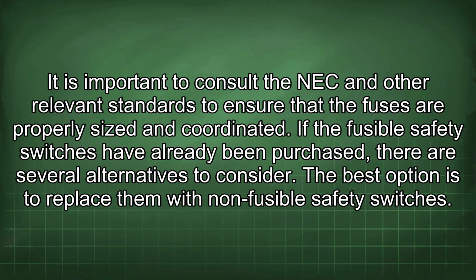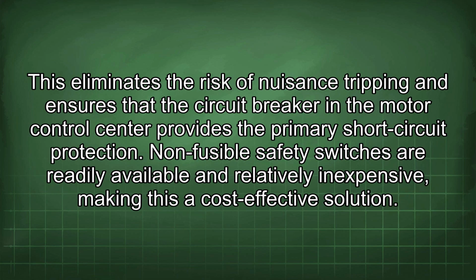It is important to consult the NEC and other relevant standards to ensure that the fuses are properly sized and coordinated. If the fusible safety switches have already been purchased, there are several alternatives to consider. The best option is to replace them with non-fusible safety switches. This eliminates the risk of nuisance tripping and ensures that the circuit breaker in the motor control center provides the primary short circuit protection. Non-fusible safety switches are readily available and relatively inexpensive, making this a cost-effective solution.